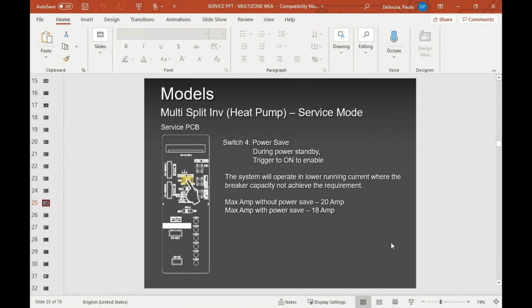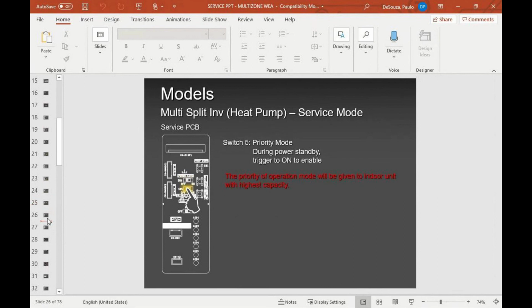If you have a power outage, that memory can be easily cancelled if you have a power outage of about 48 to 76 hours. So I would not advise you to use that wiring check. The best way to do it is turn on 1 unit at a time, as I mentioned to you a few seconds ago. So please, if you can, avoid using the wiring check option.